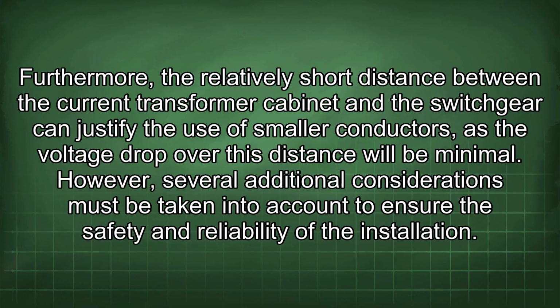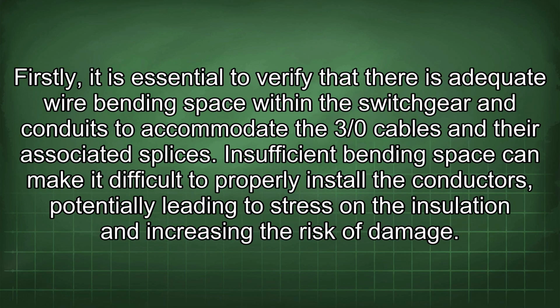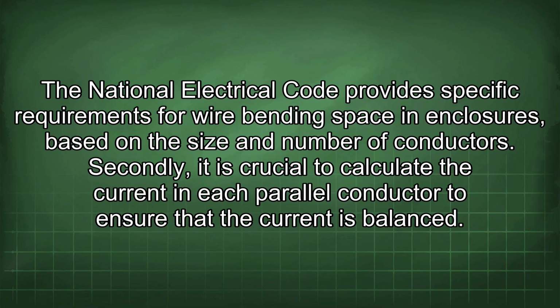However, several additional considerations must be taken into account to ensure the safety and reliability of the installation. Firstly, it is essential to verify that there is adequate wire bending space within the switchgear and conduits to accommodate the 3/0 cables and their associated splices. Insufficient bending space can make it difficult to properly install the conductors, potentially leading to stress on the insulation and increasing the risk of damage. The National Electrical Code provides specific requirements for wire bending space in enclosures, based on the size and number of conductors.